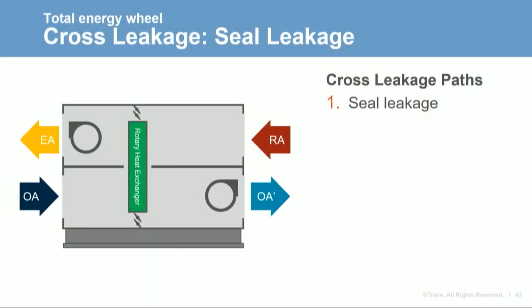Cross leakage can be wasteful and result in the system fans having to move more air than originally required. The system design can reduce cross leakage and minimize its impact. The first and largest source of cross leakage is at the wheel face where pressure differentials between the two air paths drive air movement — seal leakage. Air will leak from areas of higher pressure to areas of lower pressure — from the outdoor air section into the exhaust air section through the seal. Rubber non-contact blocks or nylon brushes can be used to reduce seal leakage.